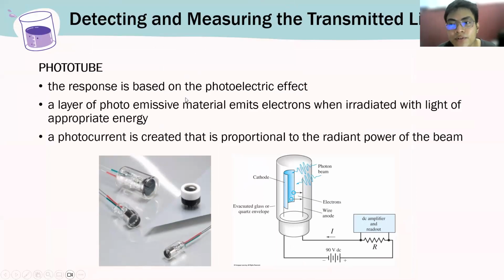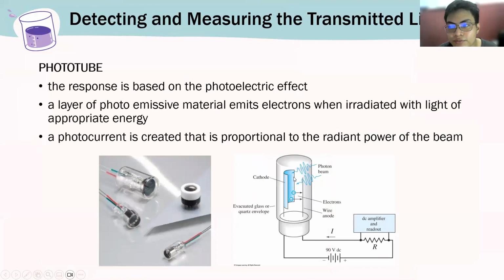Parang ito yung view niya. Zoom in tayo dito. So ito yung light source, tatama siya sa metal, and that metal electron will get ejected. So when there's a flow of electron, may kuryente. Okay? So yun yung ginagawa sa phototubes. Ang photomultiplier tube, ito yung ginagamit madalas. Why? Kasi sa phototube lang, if there's a faint amount of photons, konti lang yung photons dyan, edi sometimes the electrical signal generated is too little to be interpreted by the computer. So that's why we use the photomultiplier tube.